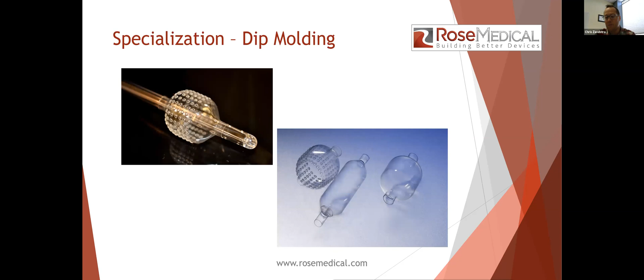But typically here you're talking about a very soft material. It's not a stent balloon, which is rigid and non-compliant. It's something that will take the shape of whatever it's inflated into. And then you can see these are a couple of balloons that we've dip molded in the past. One of them is actually mounted onto the end of a cannula there. So that's a multi-lumen cannula. We do some hole punching, we dip mold that balloon, we tip the end of it, kind of like I talked about, marrying some of those capabilities together there.